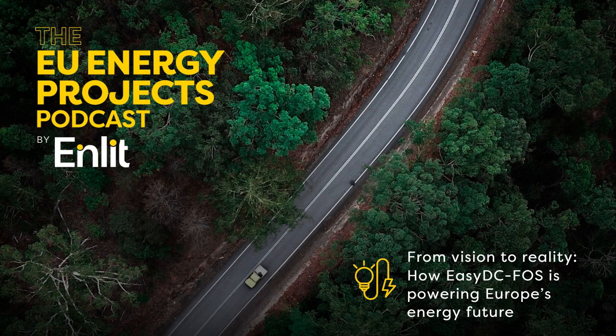This brings the advantages of direct current, which has lower energy losses. High voltage DC at 525 kV over 1,000 kilometers has half the energy loss compared to alternating current. For example, in 1,000 kilometers, you would have around 200 megawatts less energy loss than you would in an AC cable project.